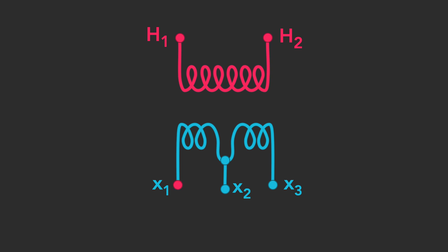Inside the unit, an end of one of the secondary windings is connected to the X1 bushing. An end of the other secondary winding is connected to the X3 bushing. The remaining ends of both windings are joined together at the X2 bushing.